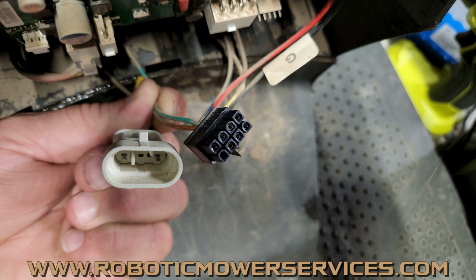Bring the end of your low voltage cable you just unplugged from the transformer around to the front of your charging station. Right here, where you have this plug that you unplugged from the circuit board in your charging station, you can test for resistance all the way from the end of your low voltage cable to the end of this plug, because the low voltage cable plugs into the back of the charging station. That charging station has a harness, and this is the other end of that harness. So you're testing that entire works right there, from the end where the transformer plugs in all the way to your circuit board. If you don't have high resistance in your positive or negative wires there, then you know that your low voltage cable is good.